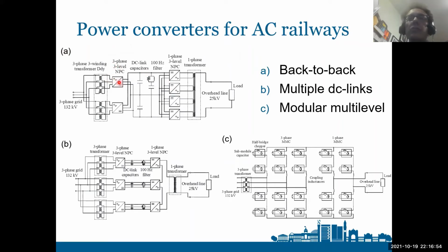We have two sections in parallel in here with two three-phase, three-level neutral point clamped active front-end converters. These are connected via this three-winding transformer with a delta star connection to reduce the harmonics on the incomer. And then there is a central DC link, which is common to the two converters in here. And then there are a number of modules, single-phase modules generating single-phase AC power, and a transformer here, which is connected in parallel or independent connection on the primary side and series connection on the secondary side to obtain the 25 kV.